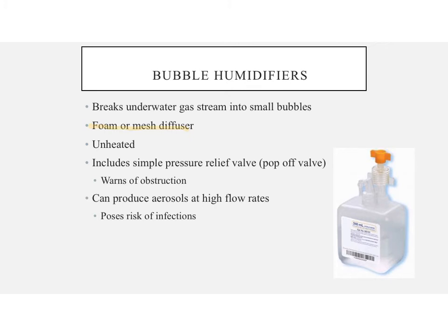It's going to make this high-pitched squealing noise, and it's very loud, but it's going to let you know that the oxygen is occluded. So this is going to help not only prevent the patient going without oxygen if the oxygen tubing is occluded, but it's also going to help prevent the bottle from bursting because of that occlusion.